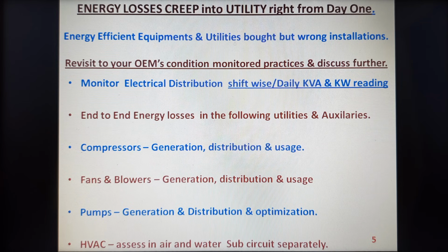Next comes the end-to-end energy losses happening in the utilities and auxiliaries. This is what we see in the compressors, fans, blowers, pumps and even in the HVAC systems: the generation, distribution and usage. What are the losses from the generation to the usage point, either in the compressed air pressure, or if it is a blower, the static pascal drop from the blower end to the delivery end.